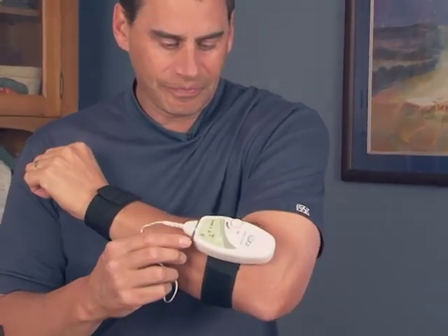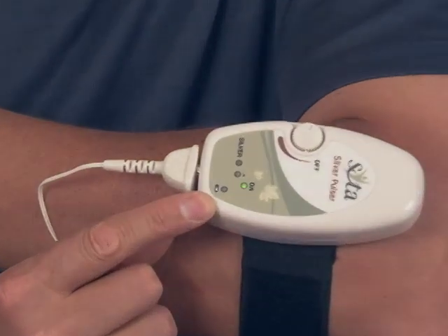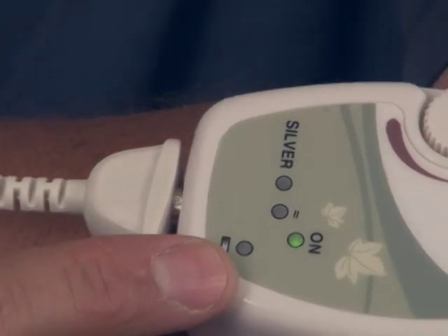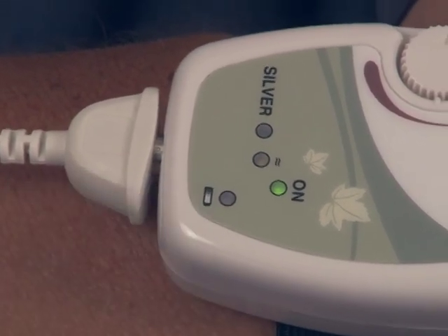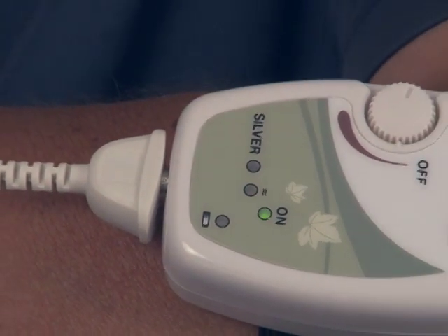When pulsing, you may find that the pulse suddenly stops. That could be caused by a low battery — the unit will drain all the charge and may suddenly stop. Turn the unit over and there's a red battery indicator light. If low battery is identified, that light will come on and you simply replace the battery. This is where rechargeables come in handy.